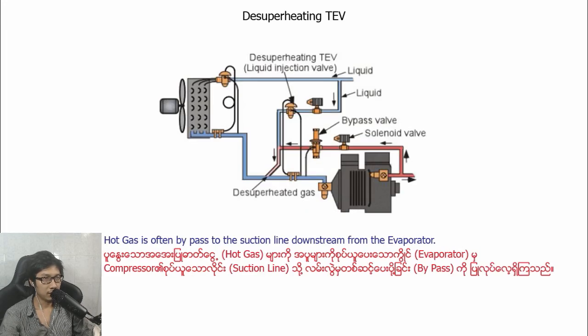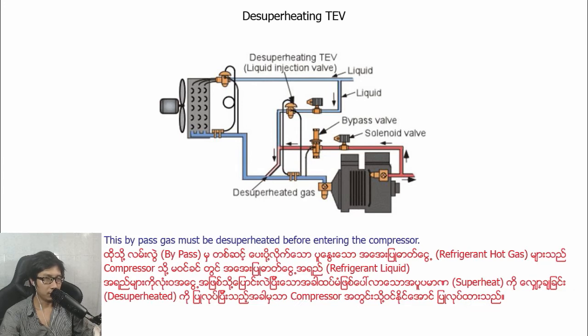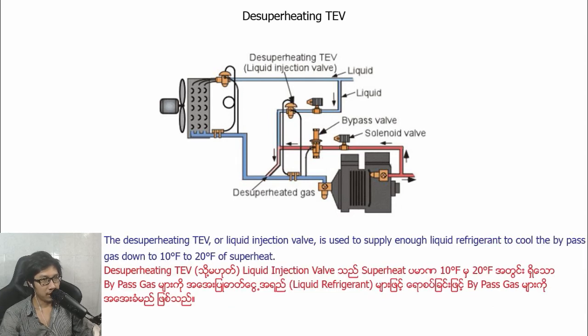Desuperheating thermostatic expansion valve (TEV). Hot gas is often bypassed to the suction line downstream of the evaporator. This bypass gas must be desuperheated before entering the compressor. The desuperheating thermostatic expansion valve (TEV) or liquid injection valve is used to supply enough liquid refrigerant to cool the bypass gas down to 10 degrees Fahrenheit to 20 degrees Fahrenheit of superheat.